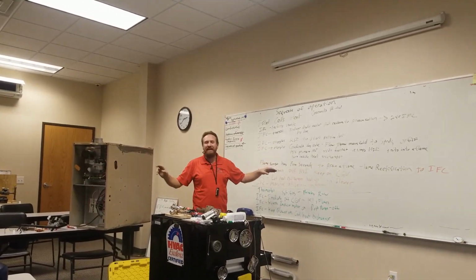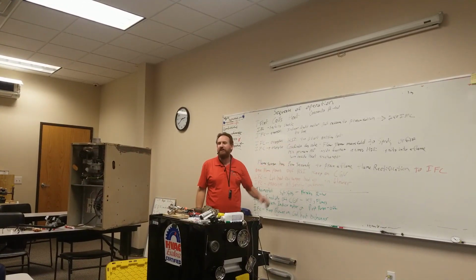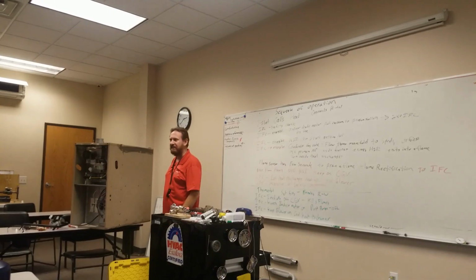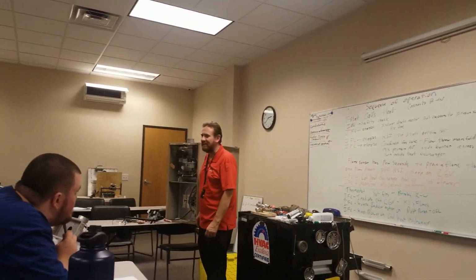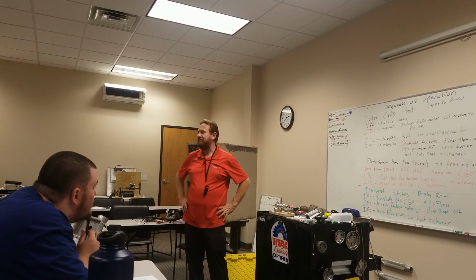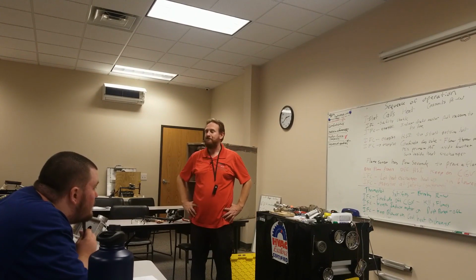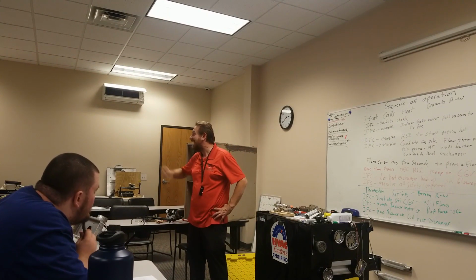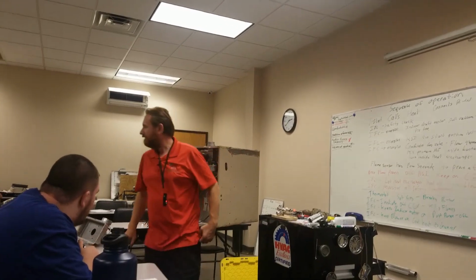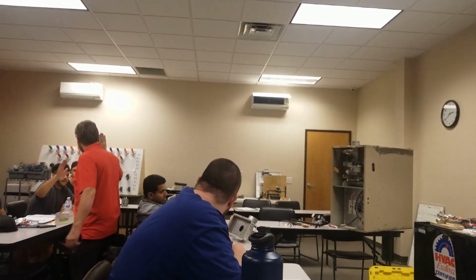That flame stays on for a few seconds and then shuts off. And then does it again. Stays on for a few seconds and then shuts off. You can see the flame. What's the problem? Flame sensor. What about it? It's dirty. Yes! That was good. That was great. Perfect.